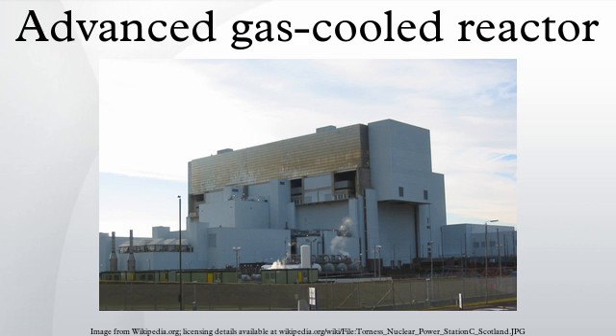In order to obtain these high temperatures yet ensure useful graphite core life, re-entrant flow of coolant at the lower boiler outlet temperature of 278 degrees Celsius is utilized to cool the graphite, ensuring that the graphite core temperatures do not vary too much from those seen in a Magnox station. The superheater outlet temperature and pressure were designed to be 2,485 psi and 543 degrees Celsius. The fuel is uranium dioxide pellets, enriched to 2.5 to 3.5 percent, in stainless steel tubes.